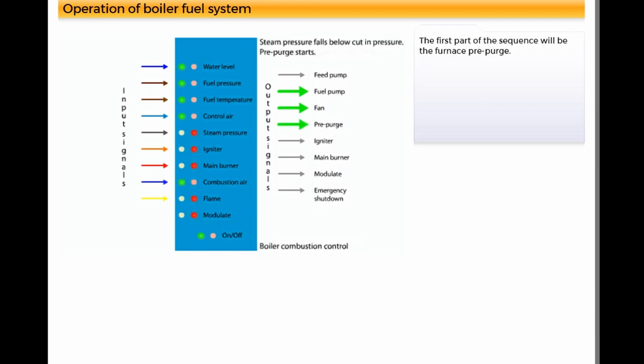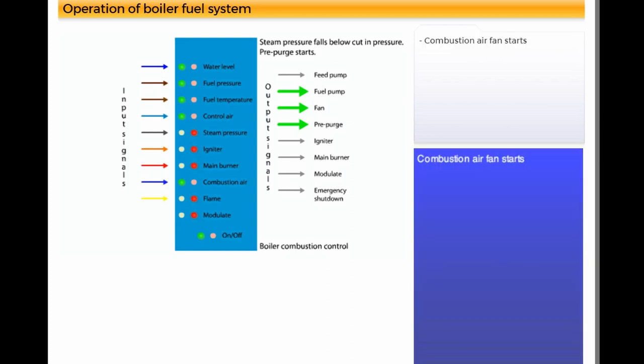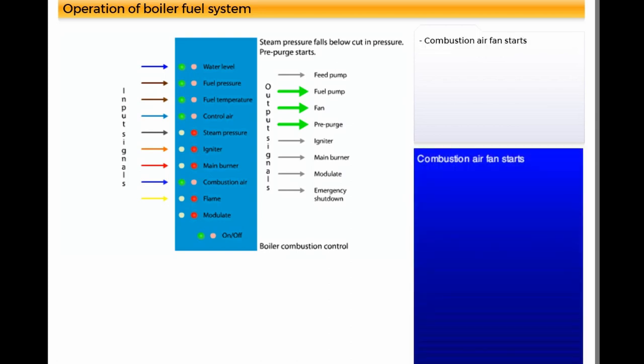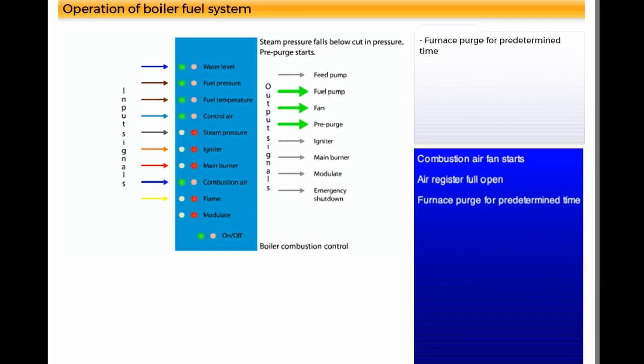The first part of the sequence will be the furnace pre-purge. Combustion air fan starts, air register full open, furnace purge for predetermined time.